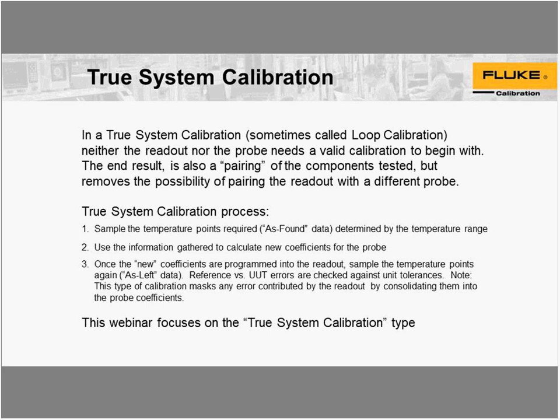Okay. Something to note here. The system is calibrated, essentially married together or linked together, because when you're doing this type of calibration, any errors that may be inherent in the readout will get focused into the data and the alignment of the probe calibration coefficients.